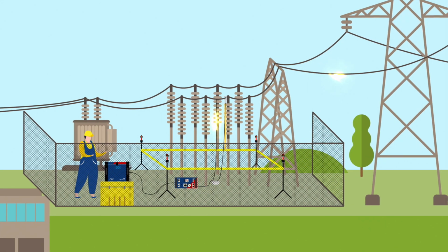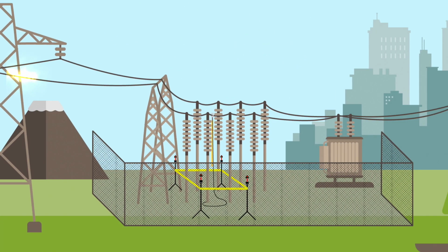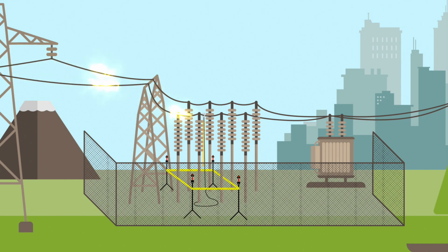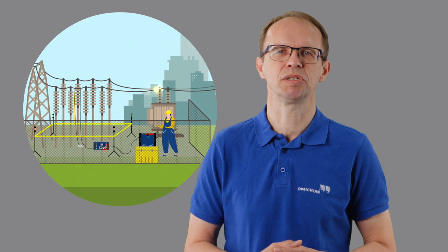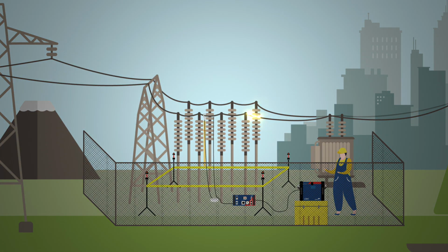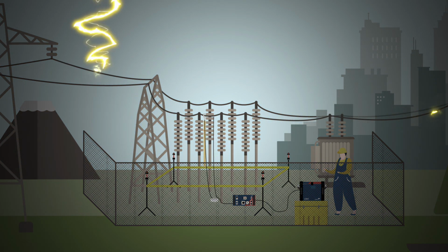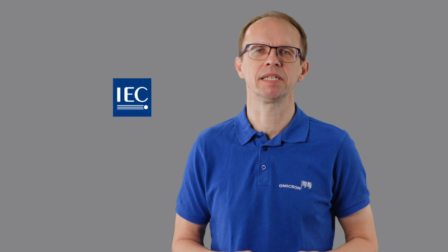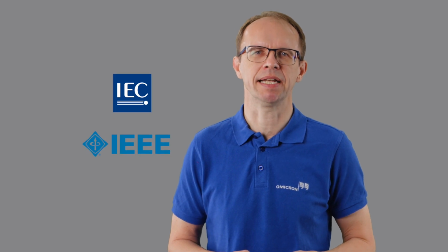With CPC 100 and CPCU1, you have a lightweight and transportable test system. Injections over long transmission lines and power cables can be covered. For unexpected events in power lines, CPCU1 protects you from dangerous voltage spikes. Line fault currents of up to 30,000 amperes are safely diverted to the ground. With our solution, the assessment is carried out according to IEC and IEEE standards.